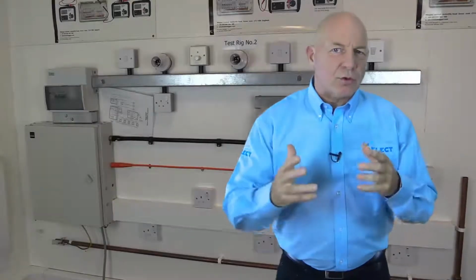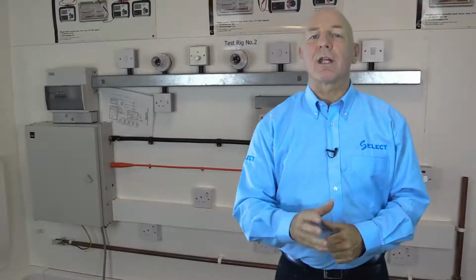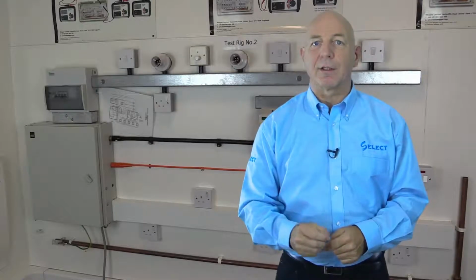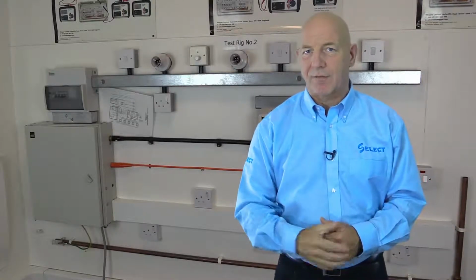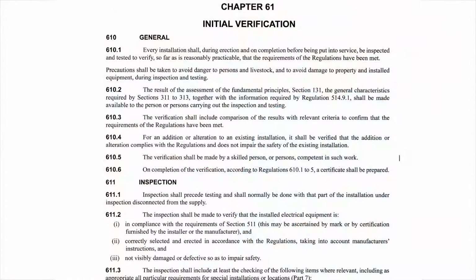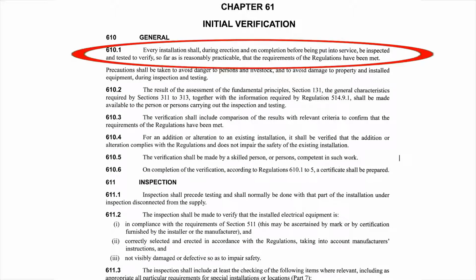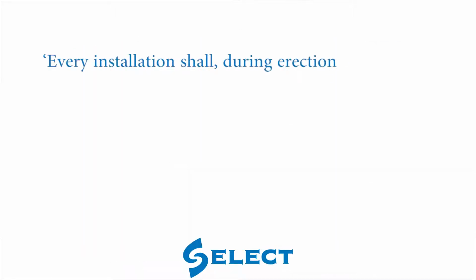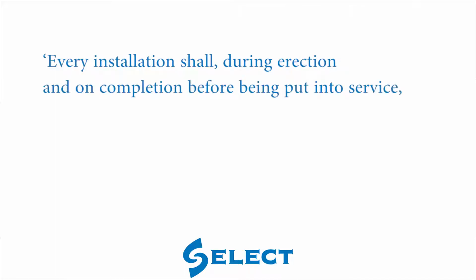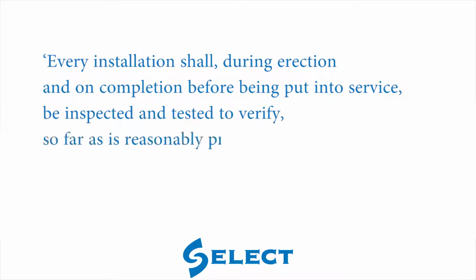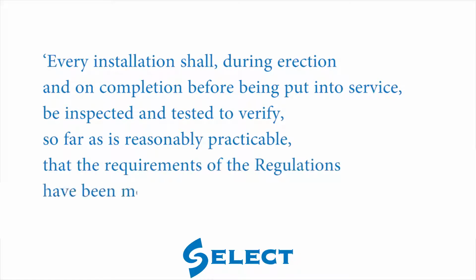However, the actual details of the inspection and tests that may have to be undertaken are given in Part 6 of BS7671. Chapter 61 provides the requirements for initial verification. Regulation 610.1 requires that every installation shall, during erection and on completion, before being put into service, be inspected and tested to verify, so far as is reasonably practicable, that the requirements of the regulations have been met.